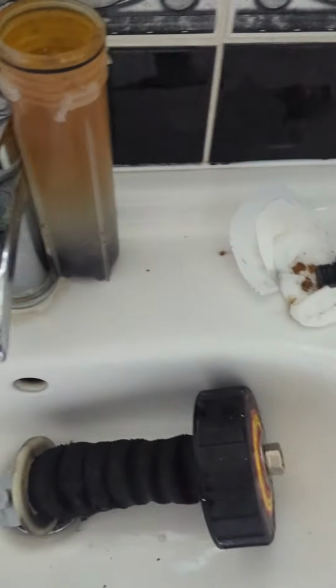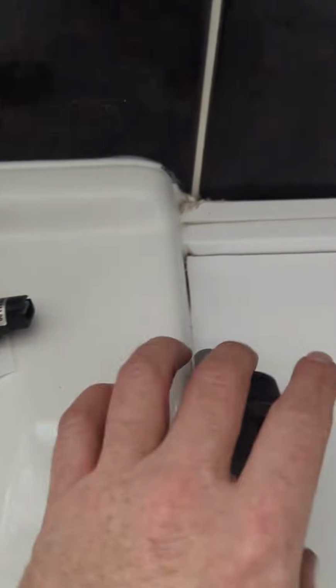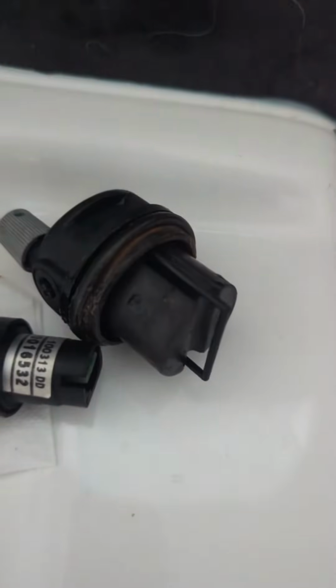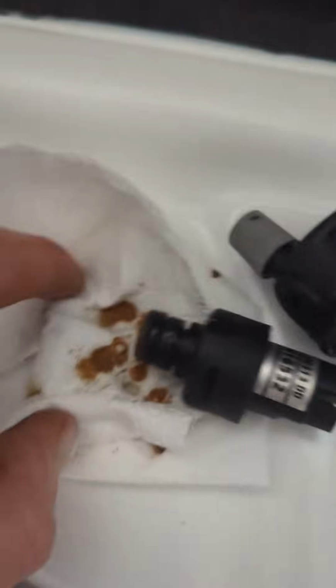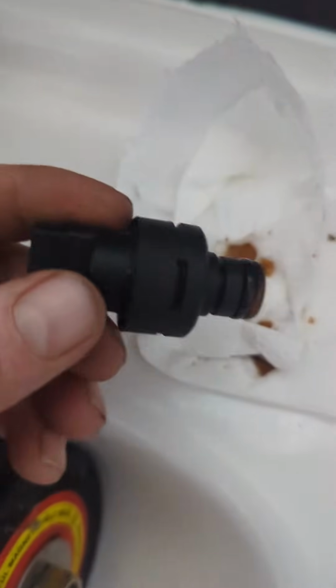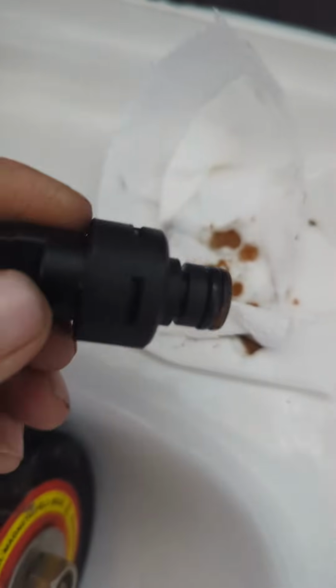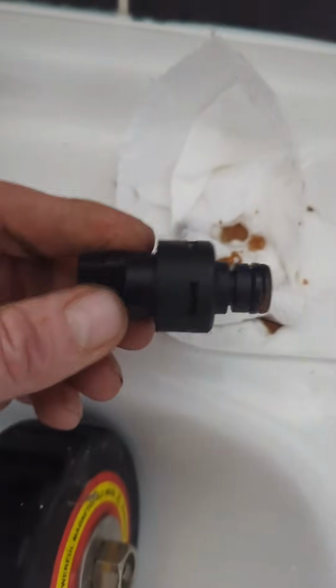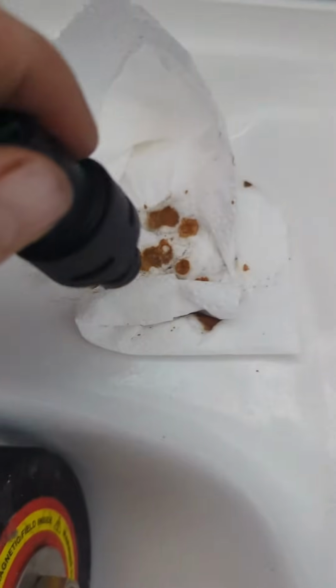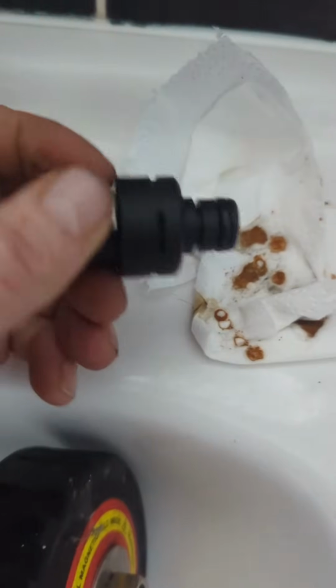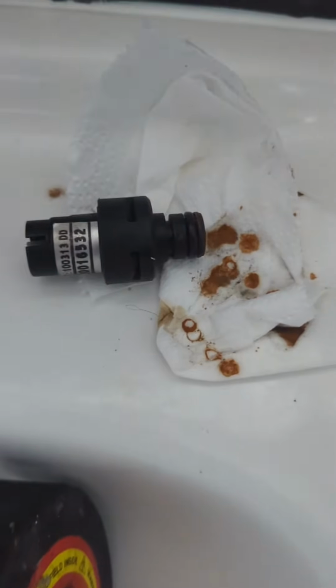These are the parts that I remove on a standard annual service. So, the automatic air vent, this is stinking. This is the pressure sensor. Now, this is a very common fault on these boilers. Most Vaillants and Glow-worms will have the same sensor. You can see it's full of muck, and what will happen is this will fail and give you an F75 fault. But if we're taking it out and cleaning it every year, we can avoid that.